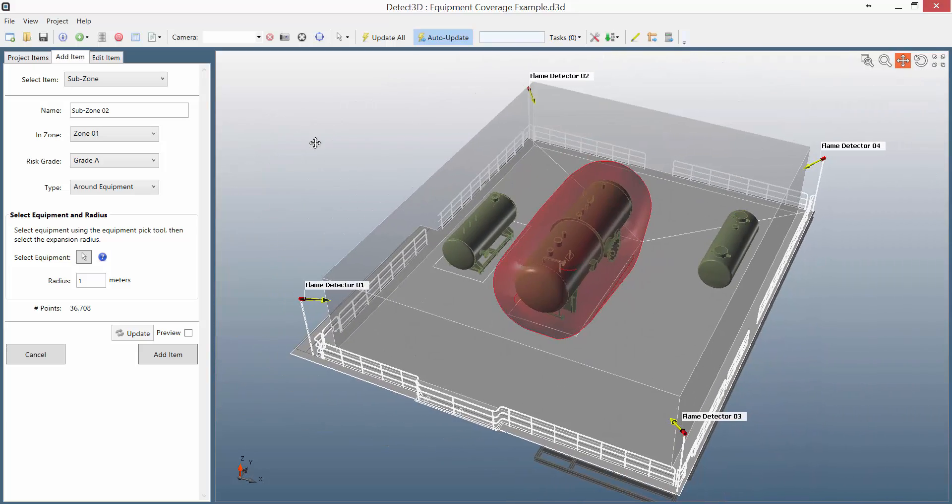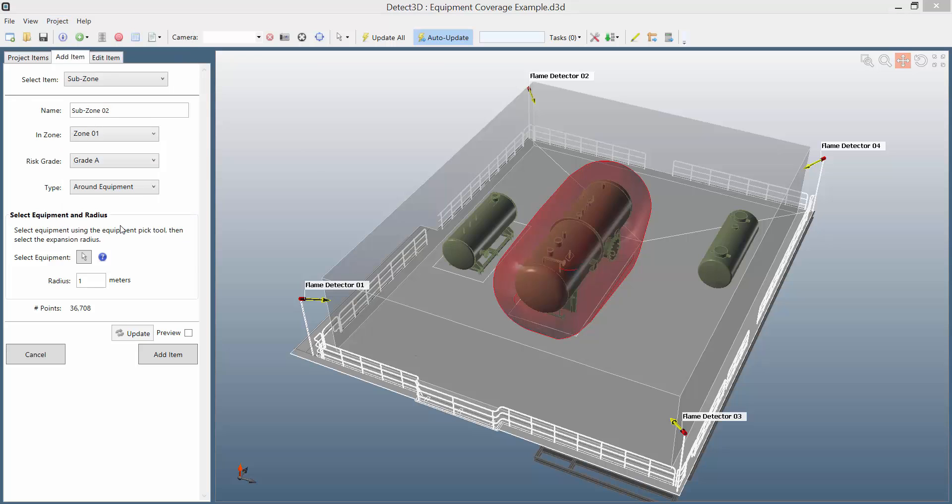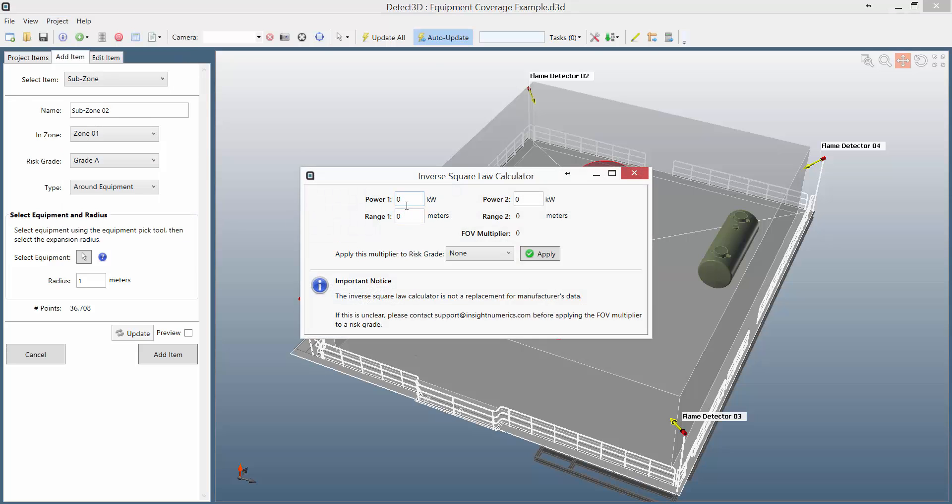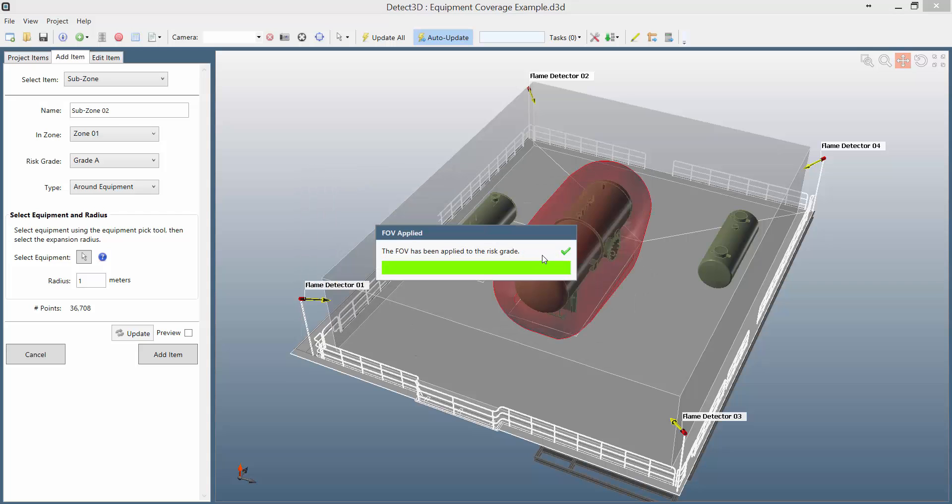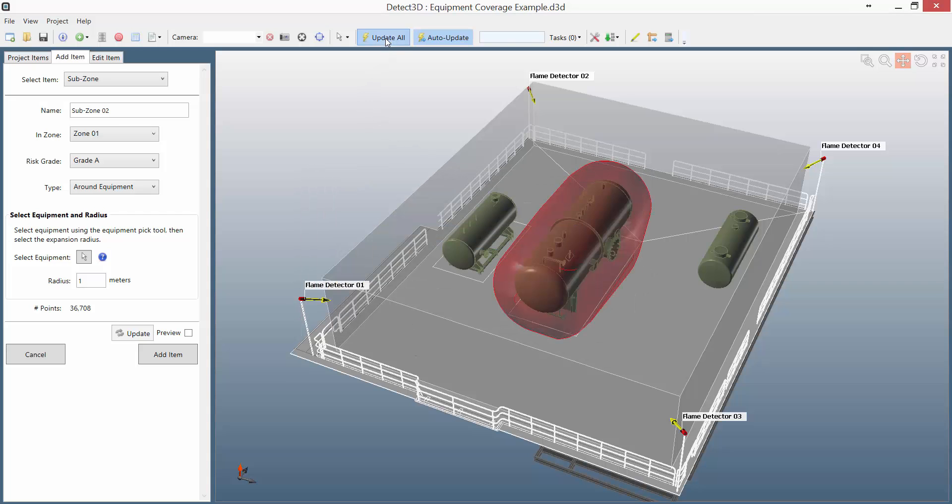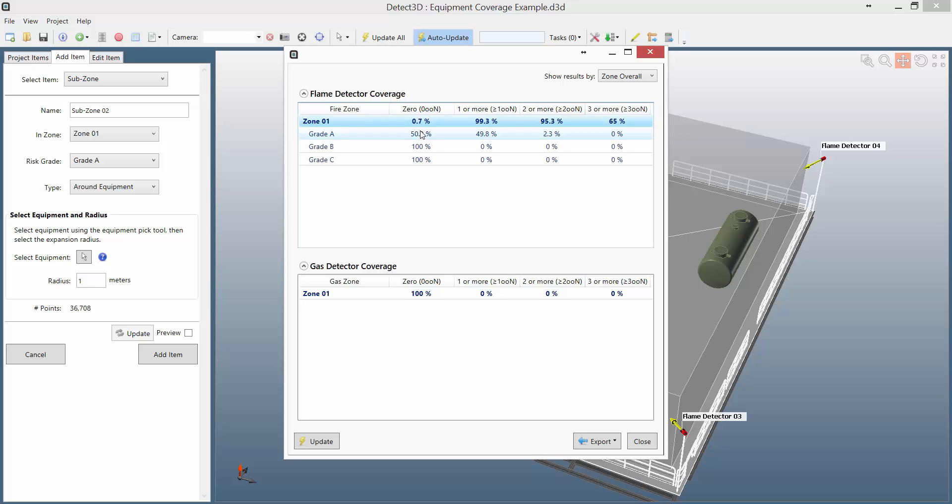Now this subzone has been assigned risk grade A. At the moment grade A is for a 10kW fire, but I can change that to 1kW fire by using the inverse square law and applying the field of view multiplier to grade A. The field of view multiplier shortens the range of the detectors, but only when the coverage for risk grade A is calculated. This means that while the overall coverage for the zone is still calculated for a 10kW fire, the risk grade A coverage is calculated for a 1kW fire.